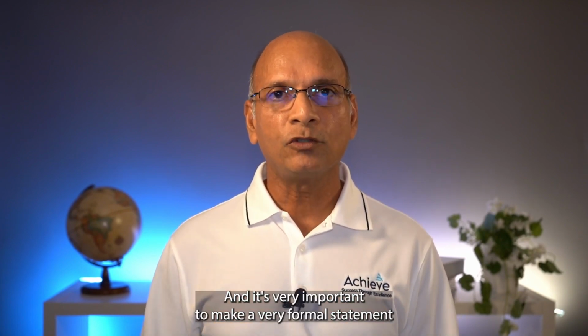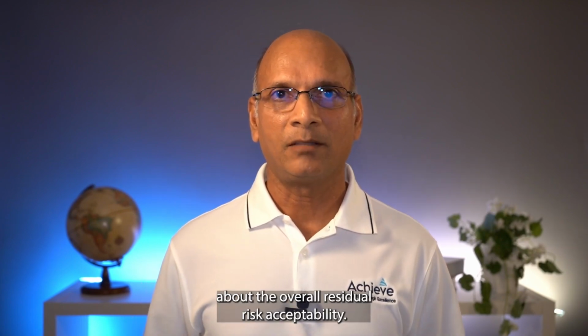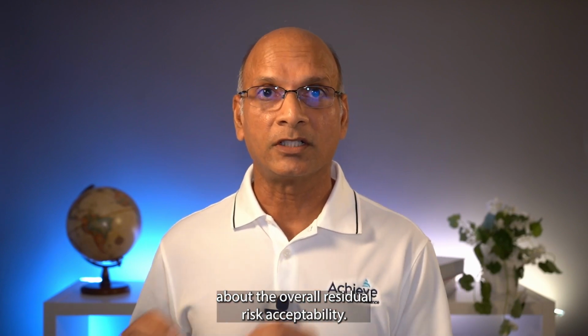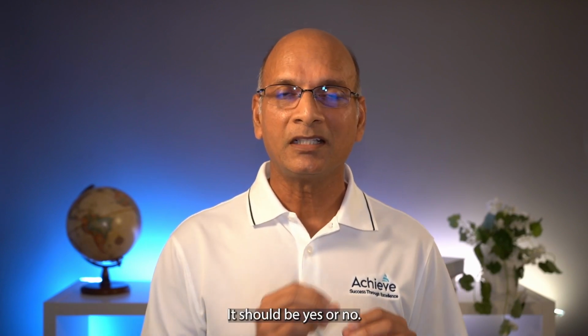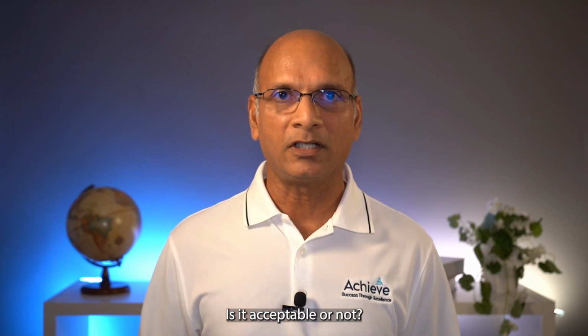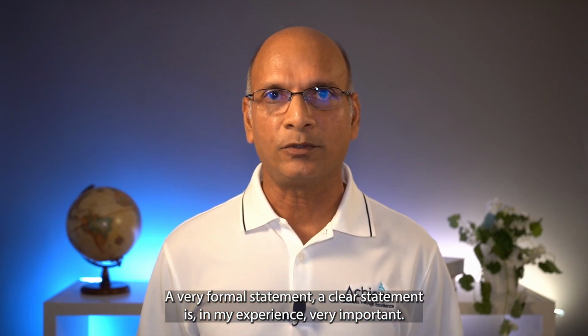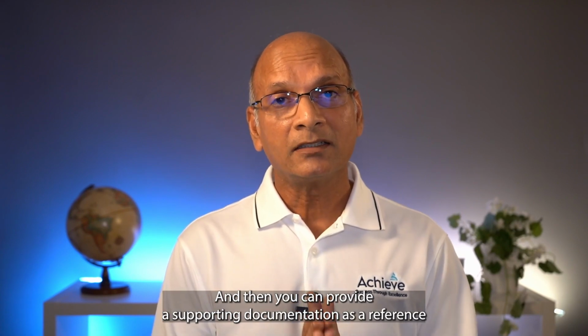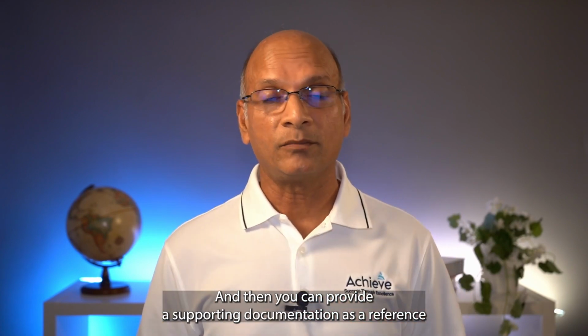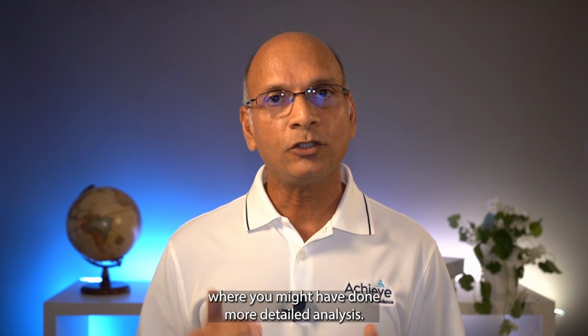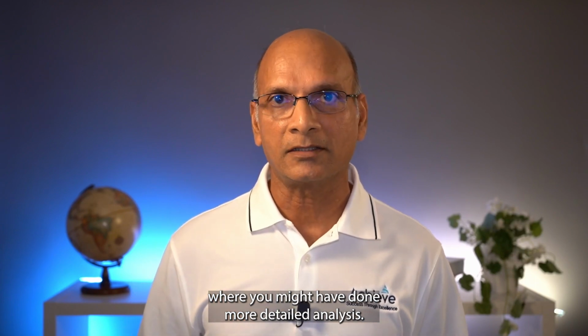And it's very important to make a very formal statement about the overall residual risk acceptability. It should be yes or no. Is it acceptable or not? A very formal, clear statement is, in my experience, very important. And then you can provide supporting documentation as a reference where you might have done more detailed analysis.